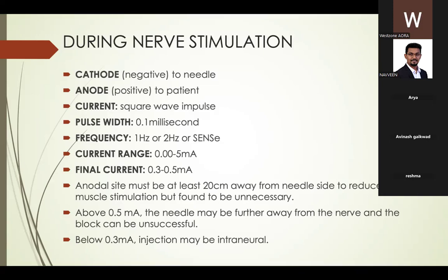The anode must be placed at least 20 centimeter away from the needle site to reduce direct muscle stimulation. But some studies have found it to be unnecessary, and it can be placed closer also. Above 0.5 milliamperes, the needle may be further away from the nerve and the block can be unsuccessful. And below 0.3 milliamperes, the injection can be intraneural. So it is always best to keep the final current between 0.3 to 0.5, or even 0.4 is the ideal final current.